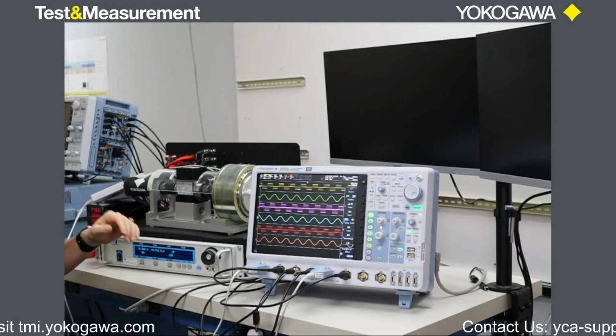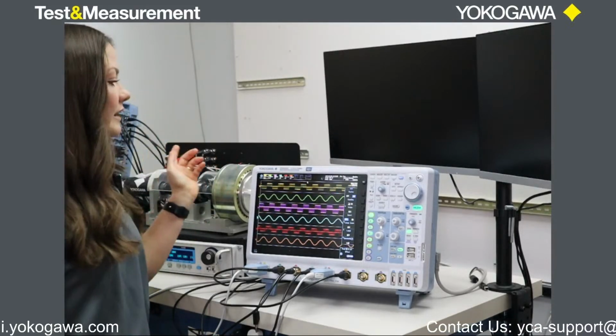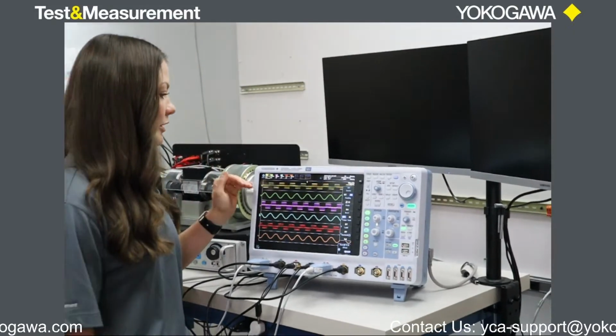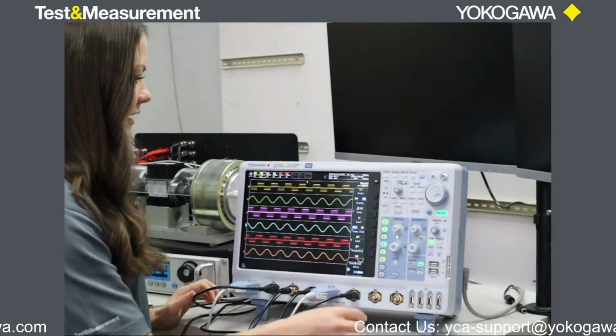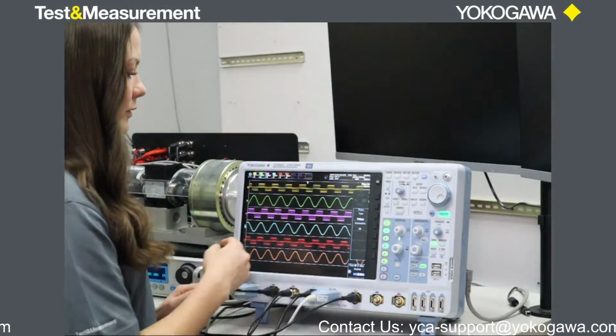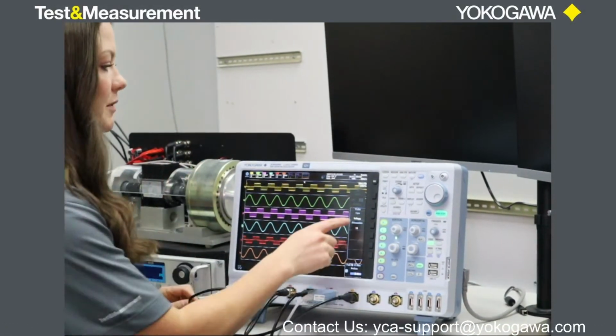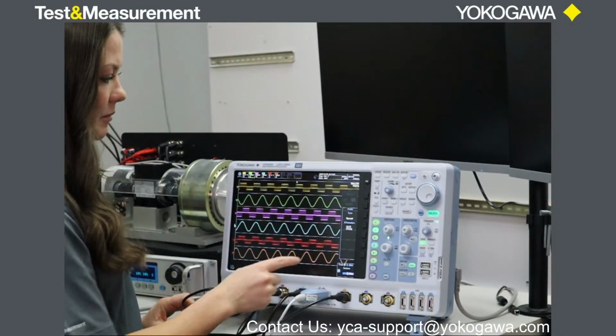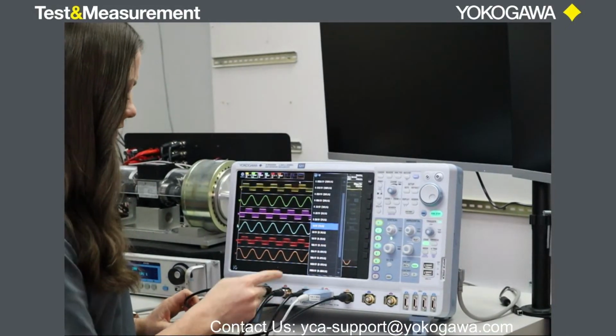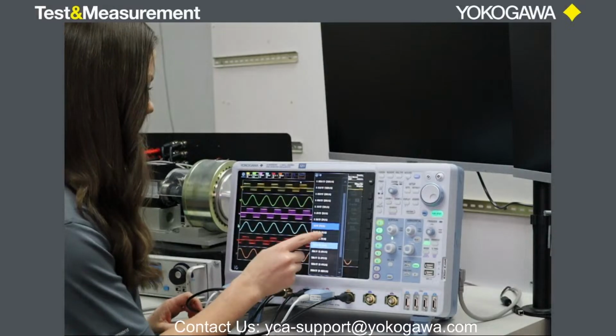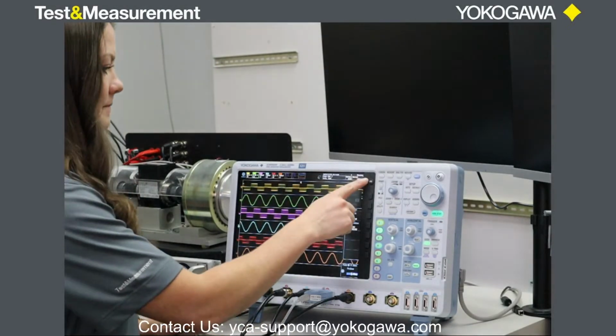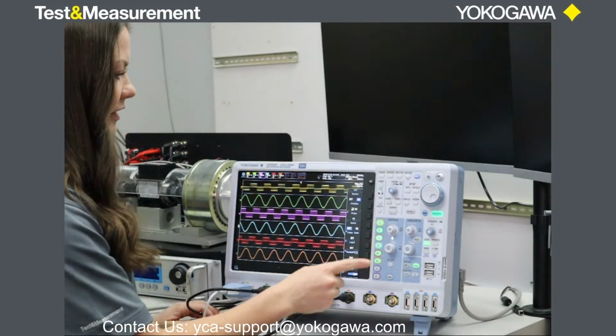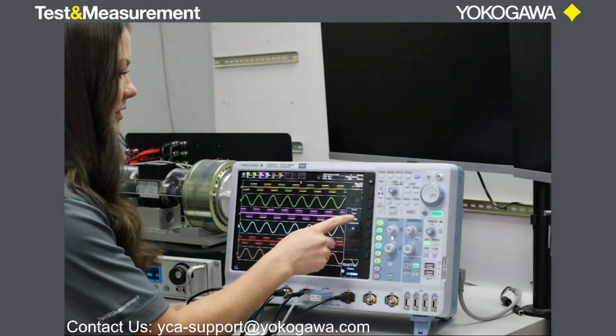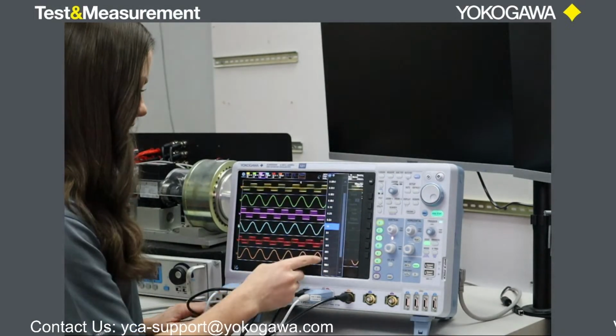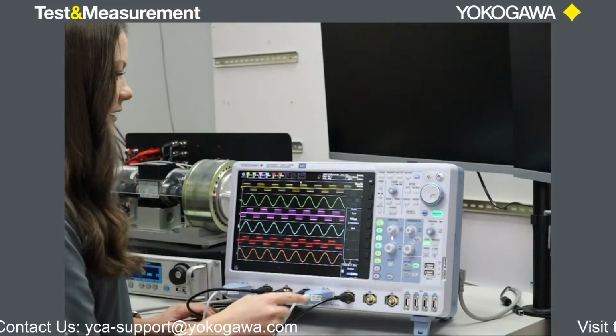They're already set. This is a 50-to-1 voltage differential probe. Now for my currents, it has the probe set as 1-to-1, so it's reading it as a voltage. But if we go in here and select current probe, we need to set this up as 10 amps to 1 volt. Then we'll just follow that for the rest of the channels. For my third voltage, we need to set 50-to-1.